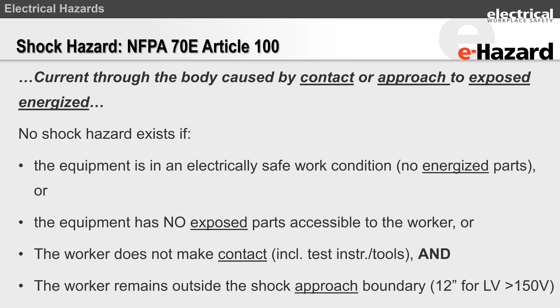When we have shock hazards, that basically means current through the body. What you have to understand is that this current is not only caused by contact, but very importantly, is also caused by approach to exposed energized conductors and circuit parts. When we talk about lower voltage, single phase, 120 volts, we're looking at contact. Then the approach falls away. But once you step above those voltages, once you're looking at 208 volts, 240 volts, and multi-phase, three-phase voltages, at low voltage, when you get within 1 foot, 12 inches, of an exposed energized conductor or circuit part, you are exposed to a shock hazard.